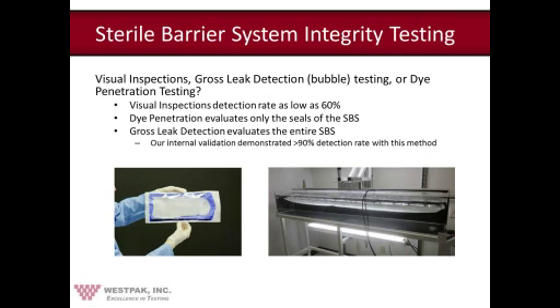And we wouldn't solely suggest relying on visual inspections for your integrity evaluation. Visual inspections based on F1886 really are just for evaluating the seals of the package, and it only has a defect detection rate as low as 60%. The human eye can only see so much. We also wouldn't suggest just going with dye penetration testing, because that really is for just evaluating the seals of your pouch or tray. It doesn't test the surface of your package, and it really is only appropriate for seal validations.